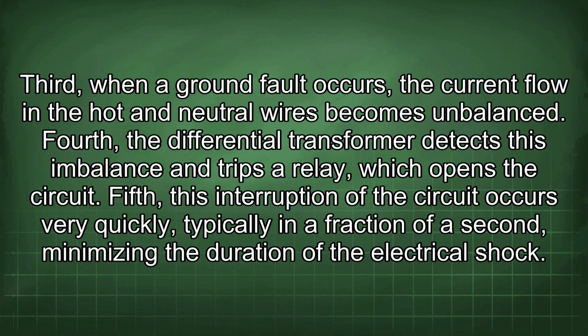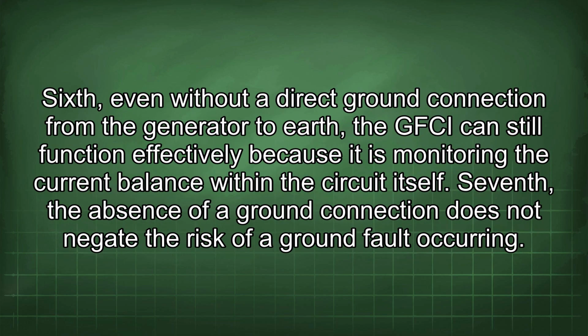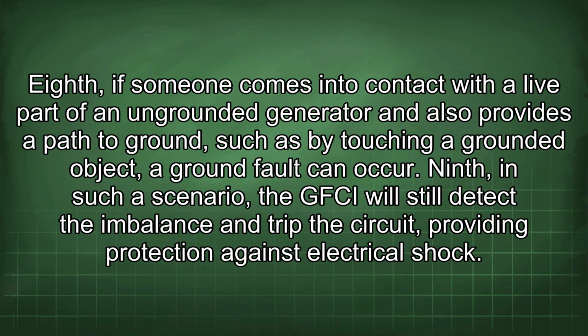Fifth, this interruption of the circuit occurs very quickly, typically in a fraction of a second, minimizing the duration of the electrical shock. Sixth, even without a direct ground connection from the generator to earth, the GFCI can still function effectively because it is monitoring the current balance within the circuit itself. Seventh, the absence of a ground connection does not negate the risk of a ground fault occurring. Eighth, if someone comes into contact with a live part of an ungrounded generator and also provides a path to ground, such as by touching a grounded object, a ground fault can occur.